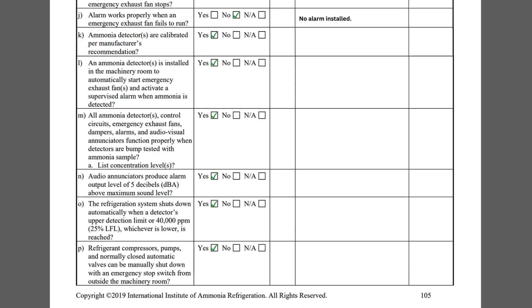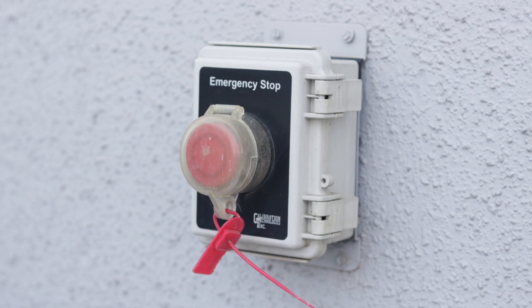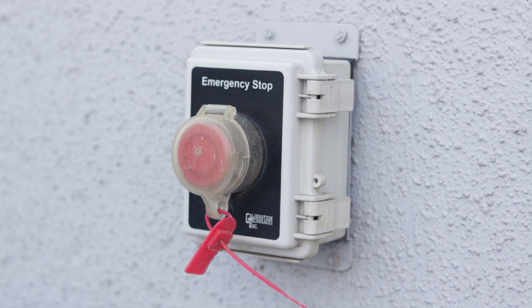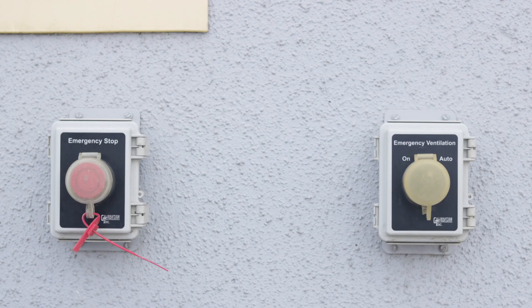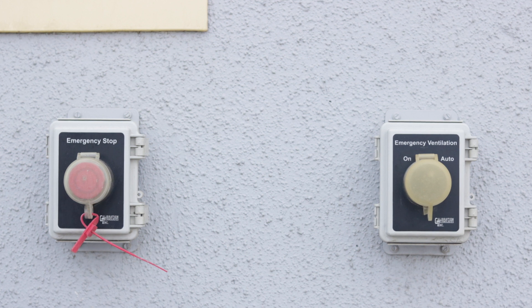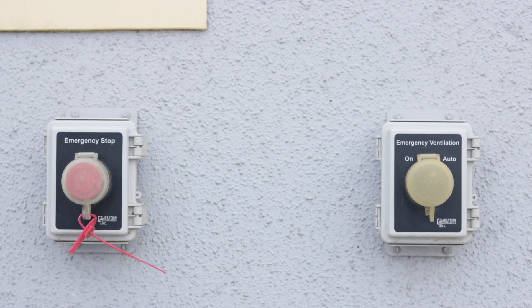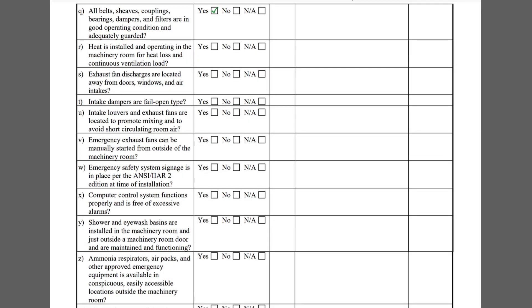Item P asks if the refrigerant compressors, pumps, and normally closed automatic valves can be manually shut down with an emergency stop switch from outside the machinery room. The emergency stop switch at this facility is properly labeled and is located within a tamper-resistant enclosure so that the stop switch cannot be activated by unauthorized personnel.